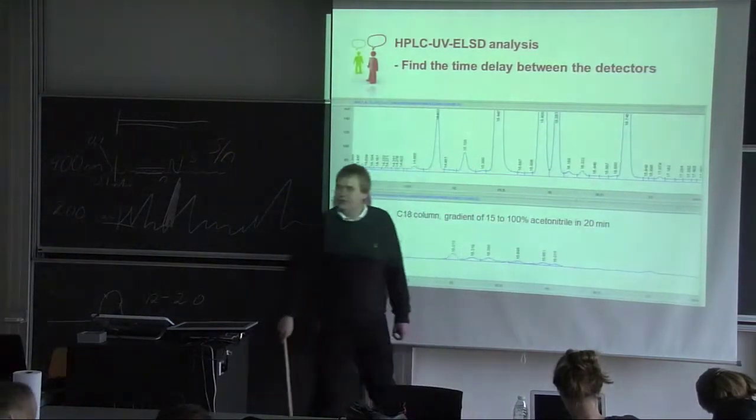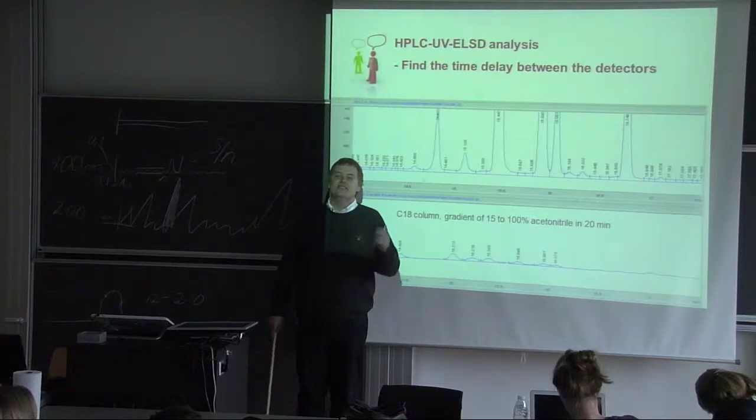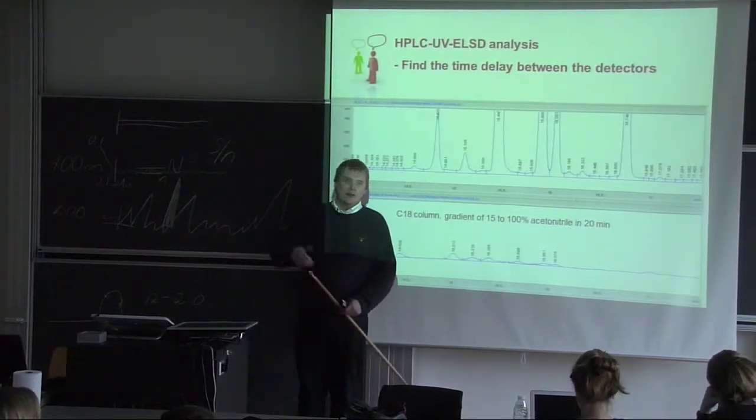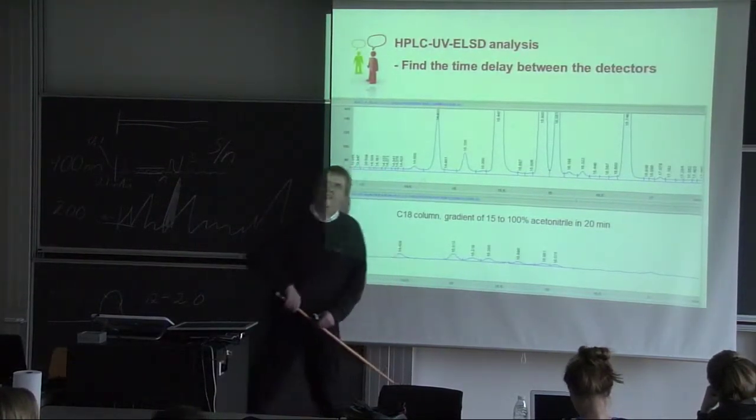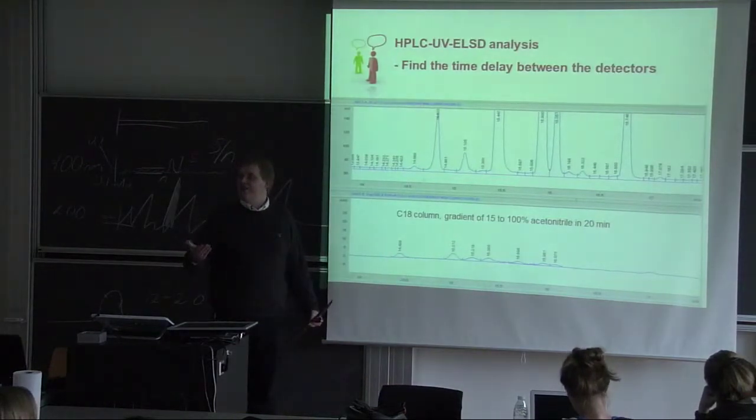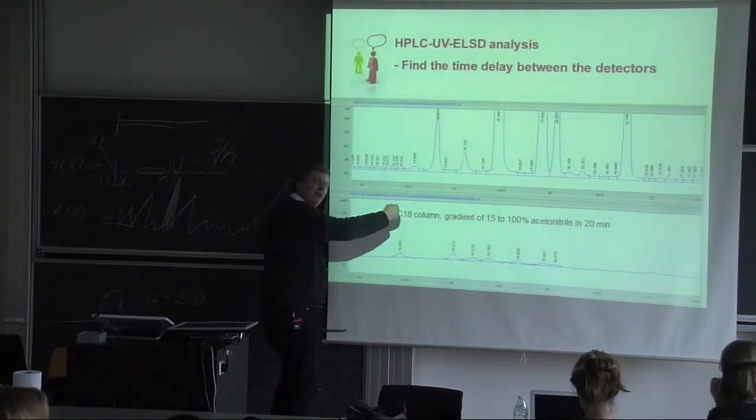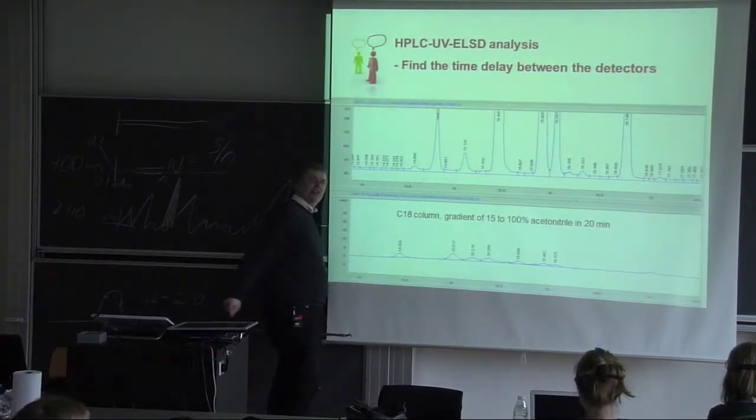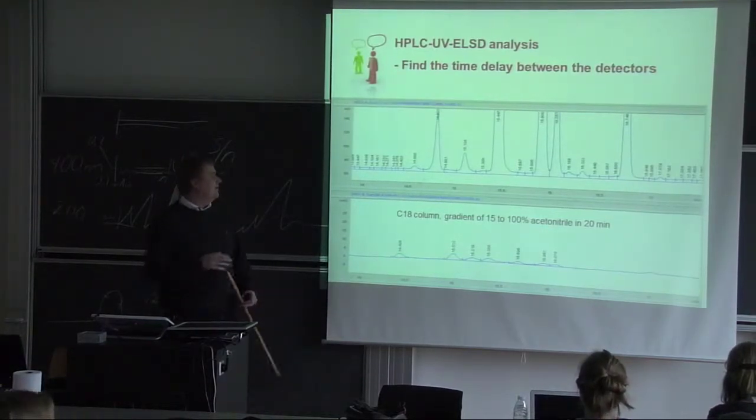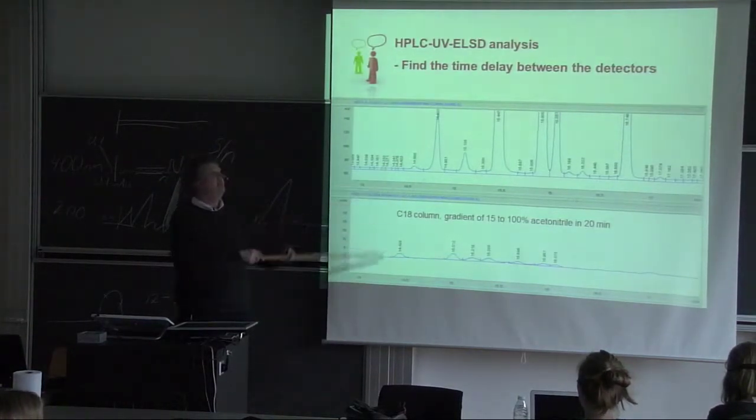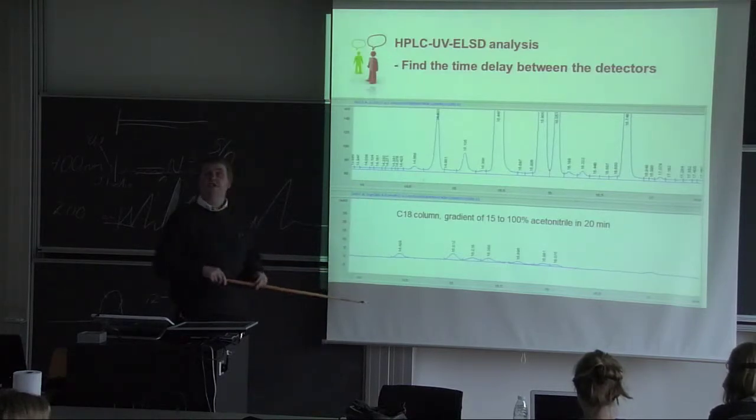So of course, to characterize this, we, of course, don't take a mixture. But a compound, you know, is UV absorbing, and you also think will be seen by evaporative light scattering. And then you characterize that, and that will be a constant time. Because that's only going to be a little bit of PEEK tubing from one detector to another, and that will have a very low volume, so you should have a very low time delay. In this case, about 0.1 seconds.